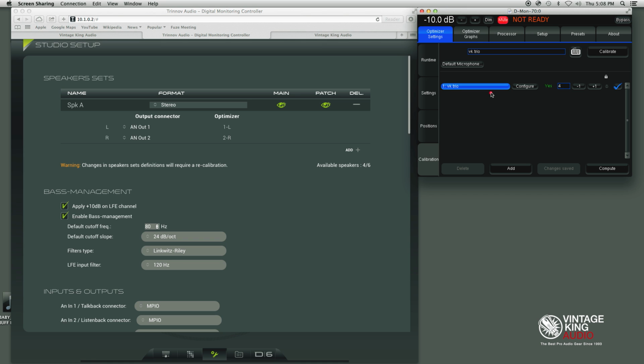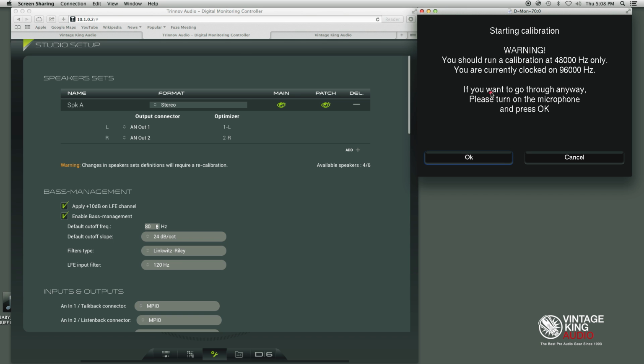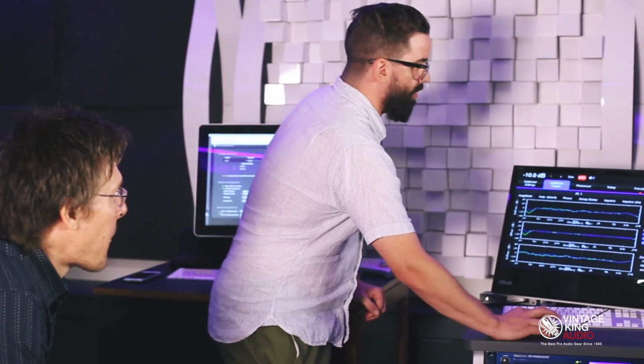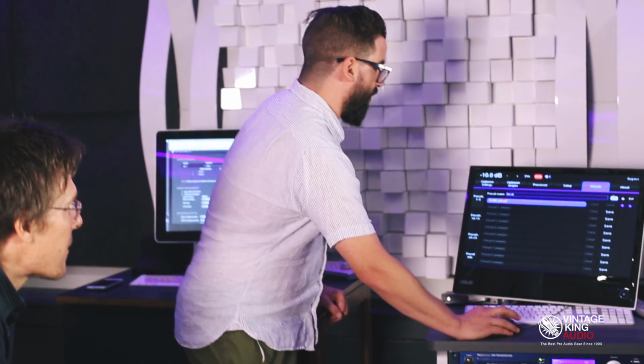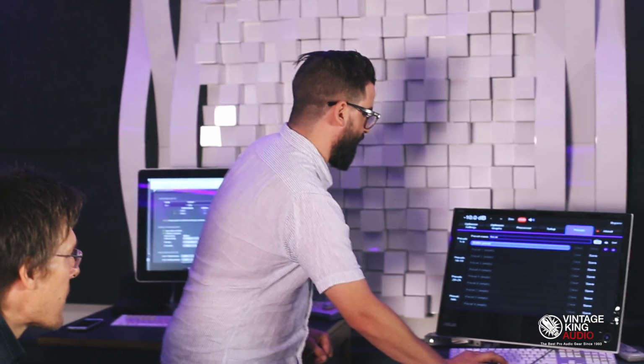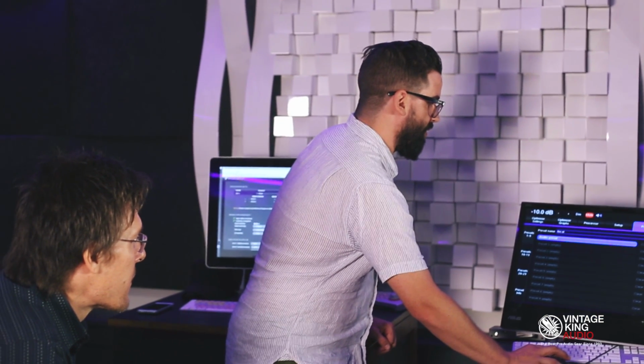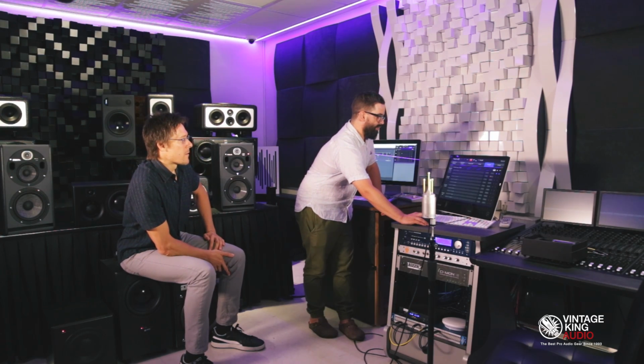So we are calibrated, and after we calibrate, we always compute. Okay. So we've calibrated and we've computed. Step that commonly gets looked over a lot. After it's computed, you always want to go back to your preset, and you want to save it. So now, saved forever until you delete it, and you want to lock it.